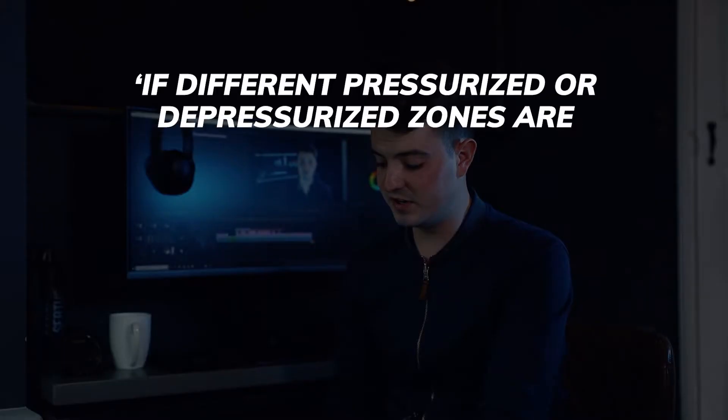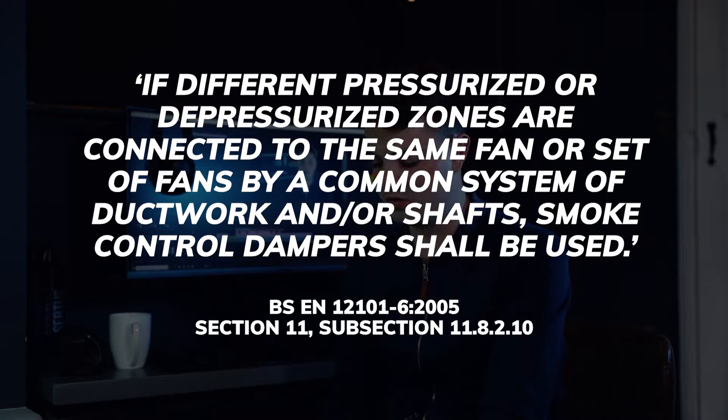When we look at BS EN 12101-6:2005, Section 11, subsection 11.8.2.10, it states that if different pressurized or depressurized zones are connected to the same fan or set of fans by a common system of ductwork and/or shafts, smoke control dampers shall be used.